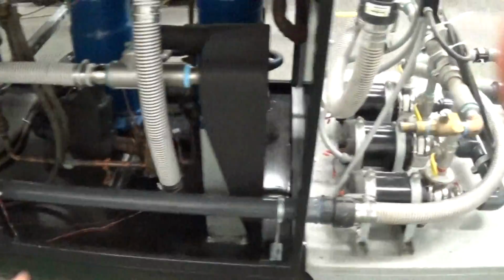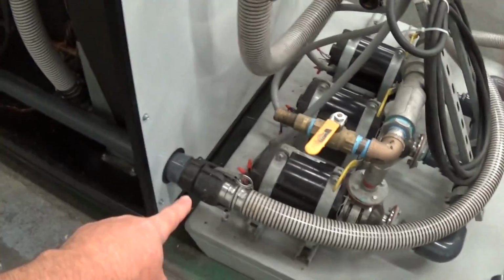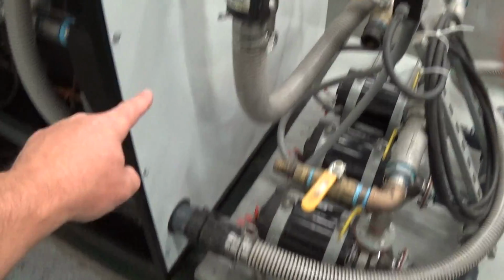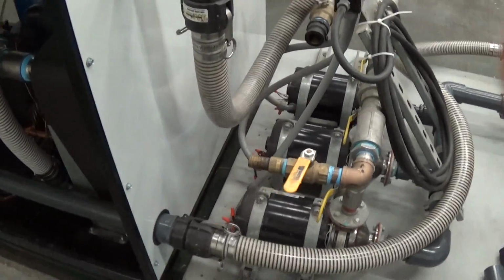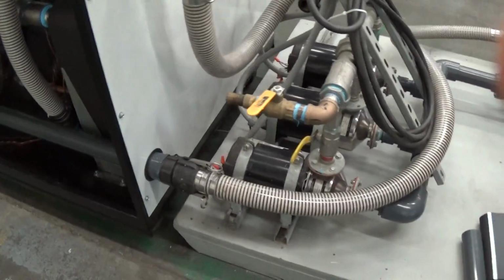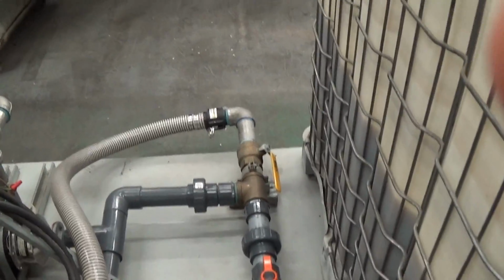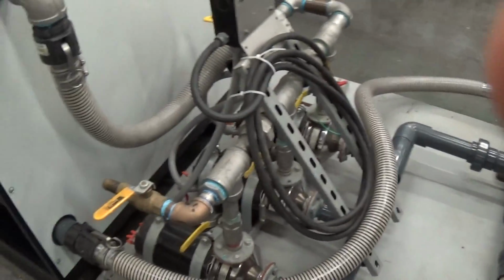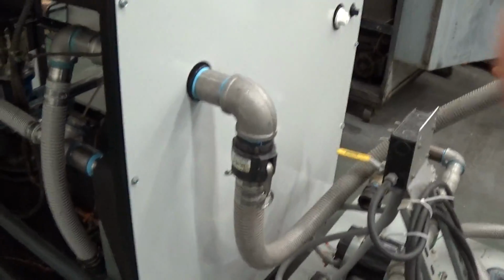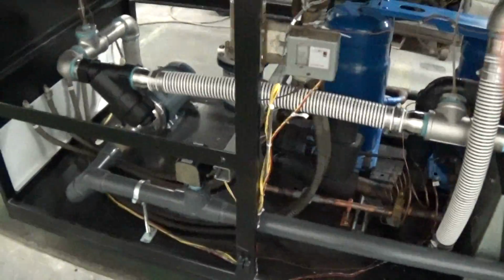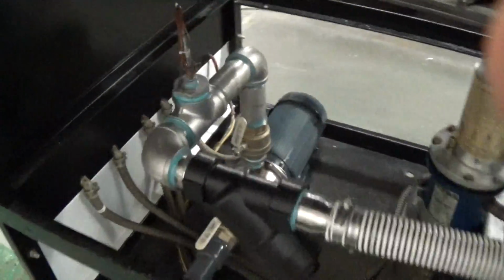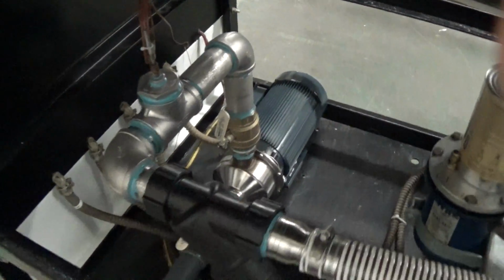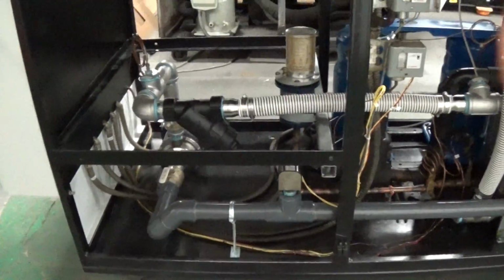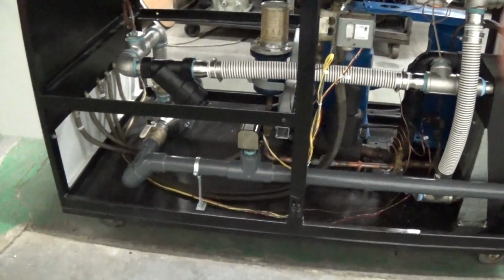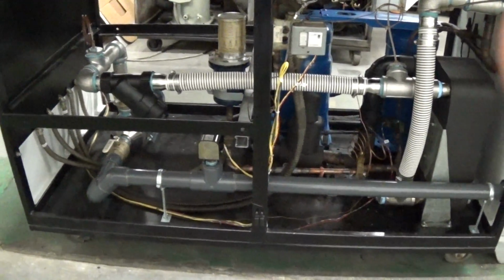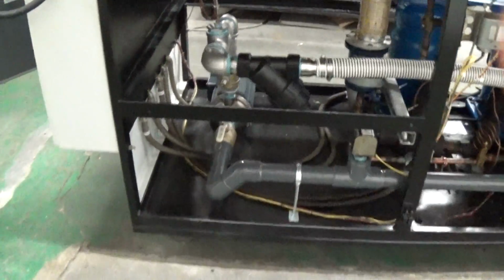In this case here, we simply have your inlet line, which is going out to our test tank, and your outlet line going to our test tank. And we're trying to see if we're throttling it. Yeah, we're throttling it a little bit back with the shut off in the tank, because your pump wants to see a little bit of back pressure. I'm sorry, we got to throttle back a little bit there. If this were a chiller that had its own internal tank, we'd have a bypass for the flow. That's not needed when you have a tankless setup like this.